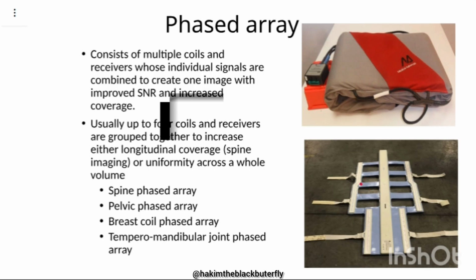For these ones, they have multiple individual coils. For example, this is a coil, coil, coil, coil, and all these ones that are branching off are coils. So every coil you see here picks up the signal from the area and sends it to this middle part. All the signal is going to be combined here and sent for processing. And even these ones are also independent coils. They have individual coils that give us individual signals, but these signals are combined and produced as a single signal.